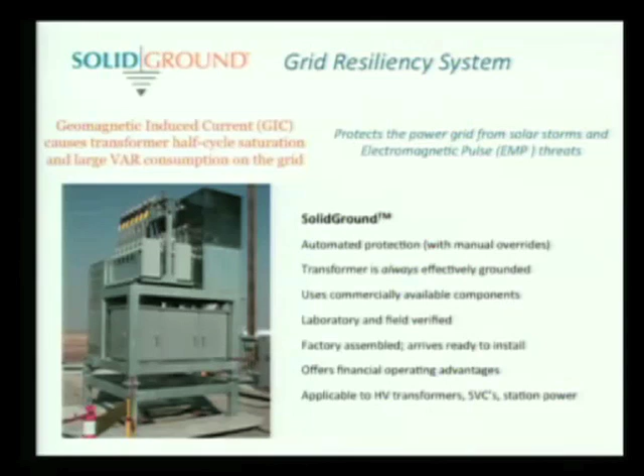Okay, here's just a brief little sketch of how this works. The transformer neutral is connected through a series of switches, a switch assembly, and then through a milliohm shunt resistor. This shunt resistor is nothing more than a large chunk of brass. So it's not really a resistor, it's just a chunk of brass. That gives us a reading. It tells us when we're seeing and measuring GIC in the neutral. At that point, or if we detect harmonics on the line, either signal will trigger the switches to open.